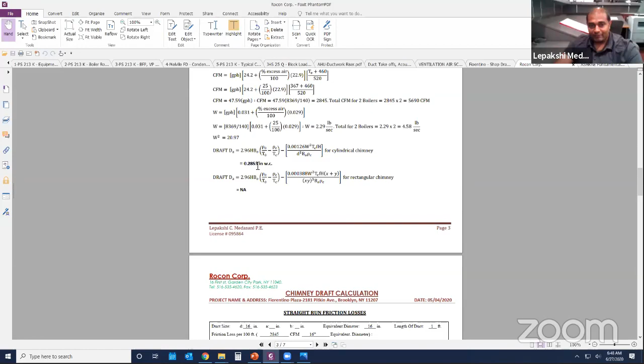As you said, the available draft we have, with just this chimney, is 0.2853 inches of water column. Our pressure we already have is the draft. So we put all that stuff in: total friction losses due to straight length ducts, that's the amount of friction losses you are getting from the straight lengths. That's the total amount of losses you are getting from the fittings like bends. This is from the transitions. This is from the converging plates. Once you add all that stuff, you'll have this 0.1916 inches of water column.